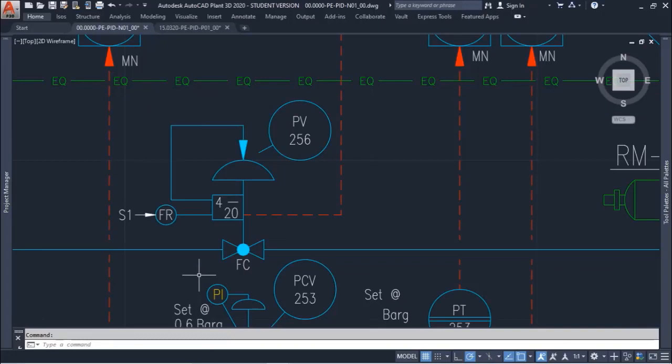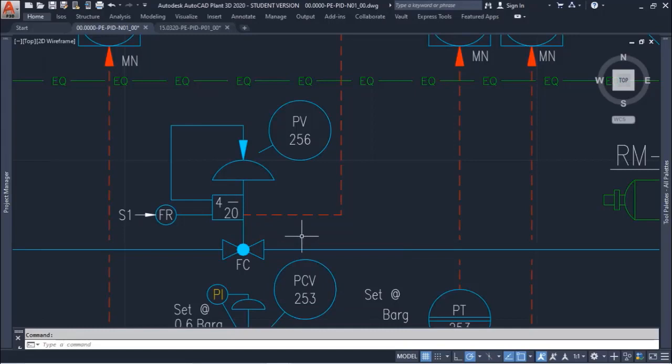In this case we have fail closed, so if the instrument air fails or is closed, this valve will automatically or mechanically close because it needs instrument air to operate.